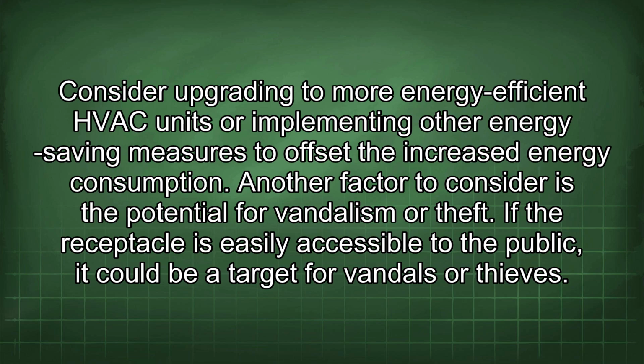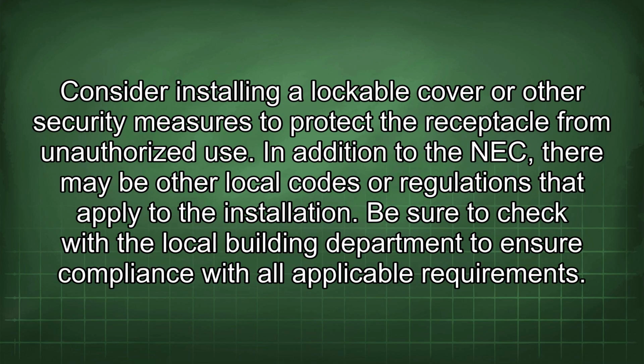Another factor to consider is the potential for vandalism or theft. If the receptacle is easily accessible to the public, it could be a target for vandals or thieves. Consider installing a lockable cover or other security measures to protect the receptacle from unauthorized use. In addition to the NEC, there may be other local codes or regulations that apply to the installation. Be sure to check with the local building department to ensure compliance with all applicable requirements.